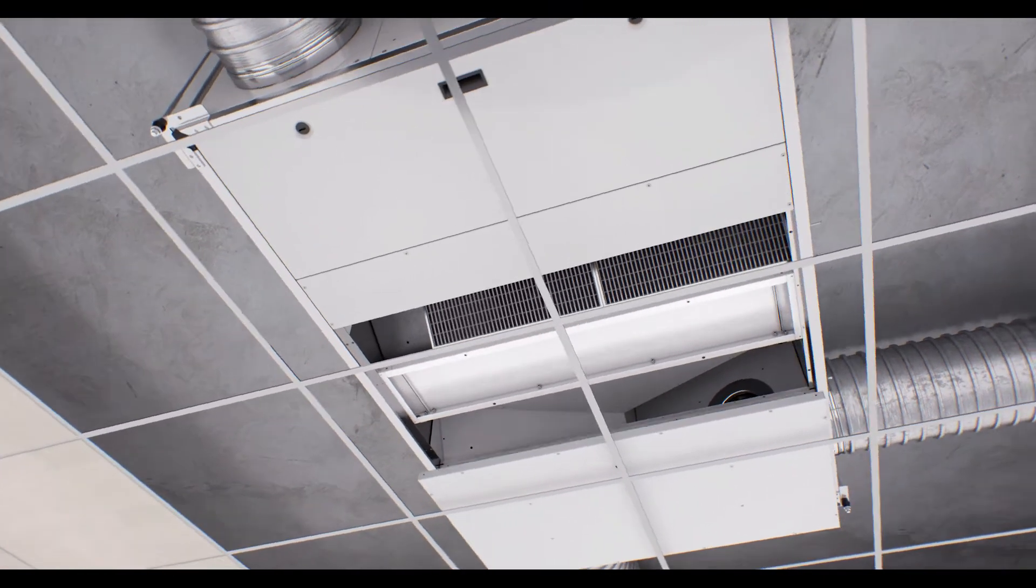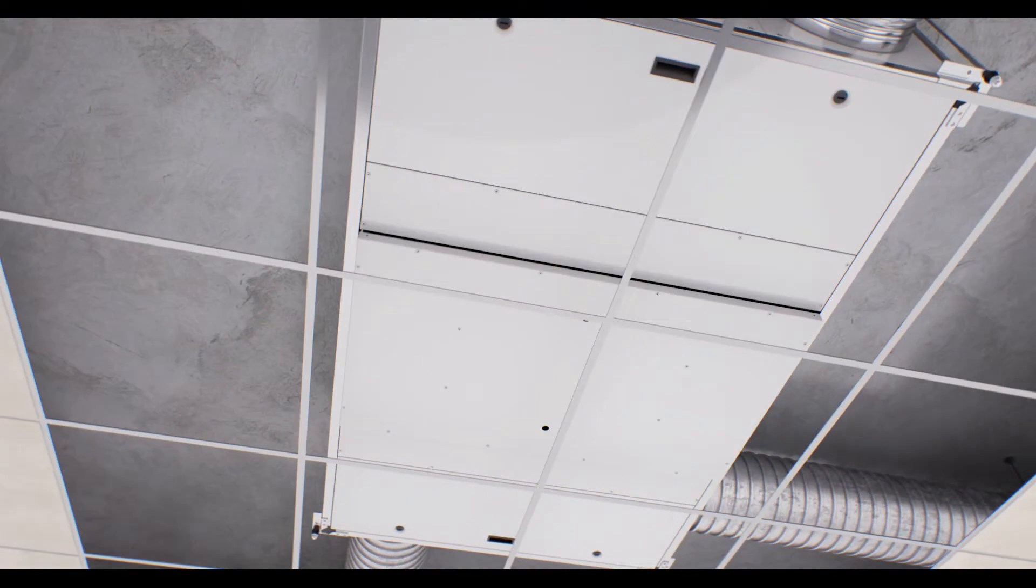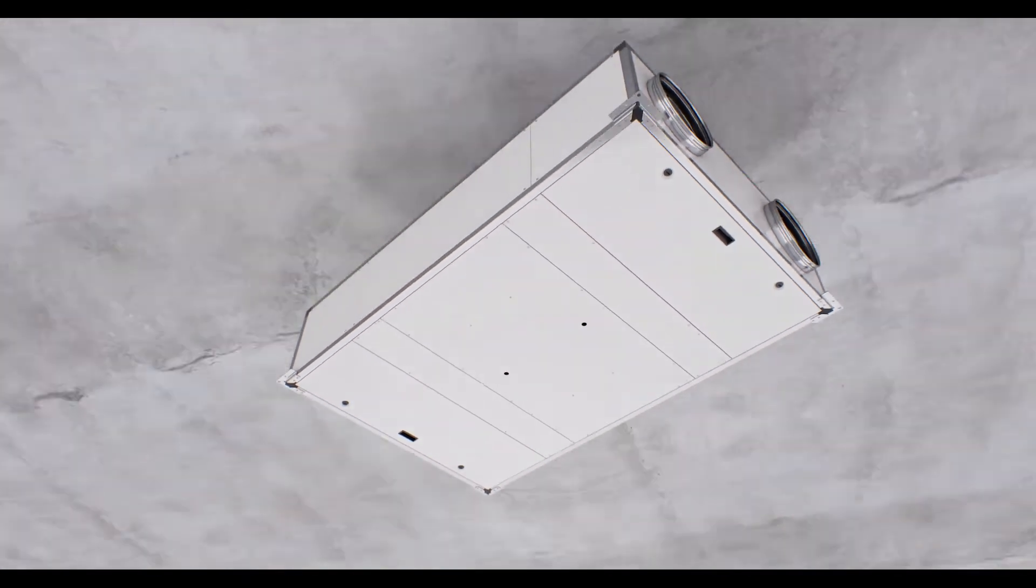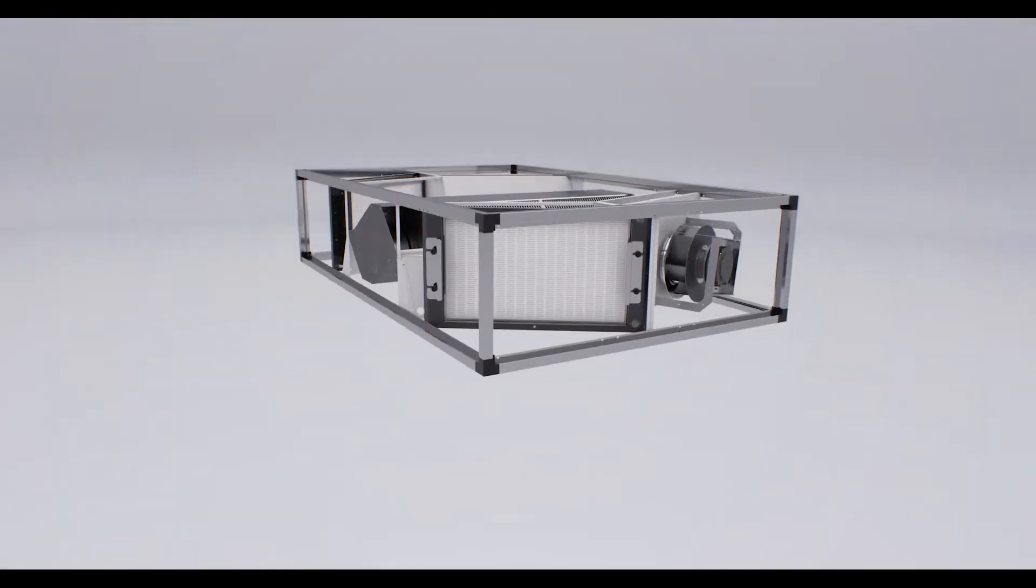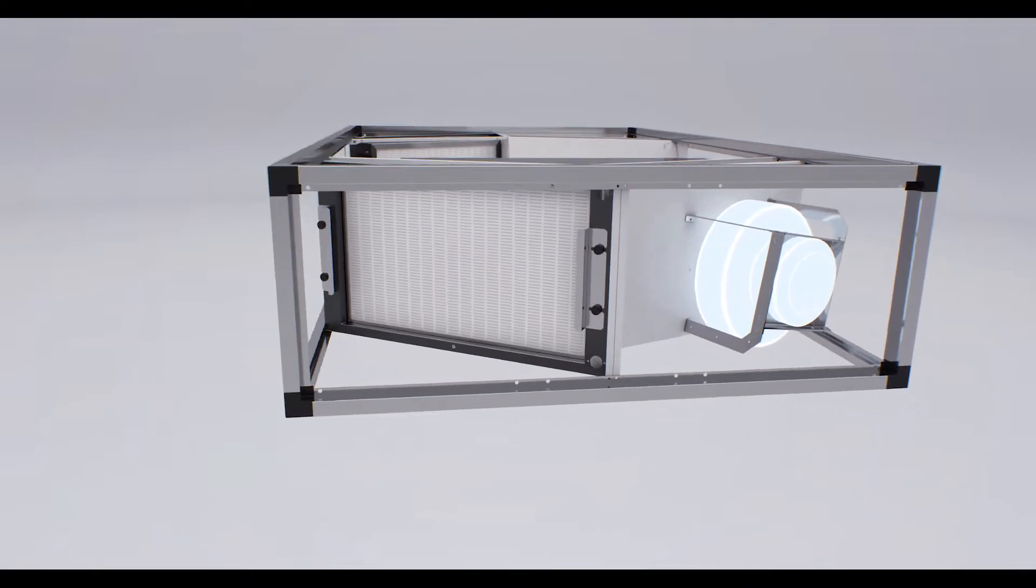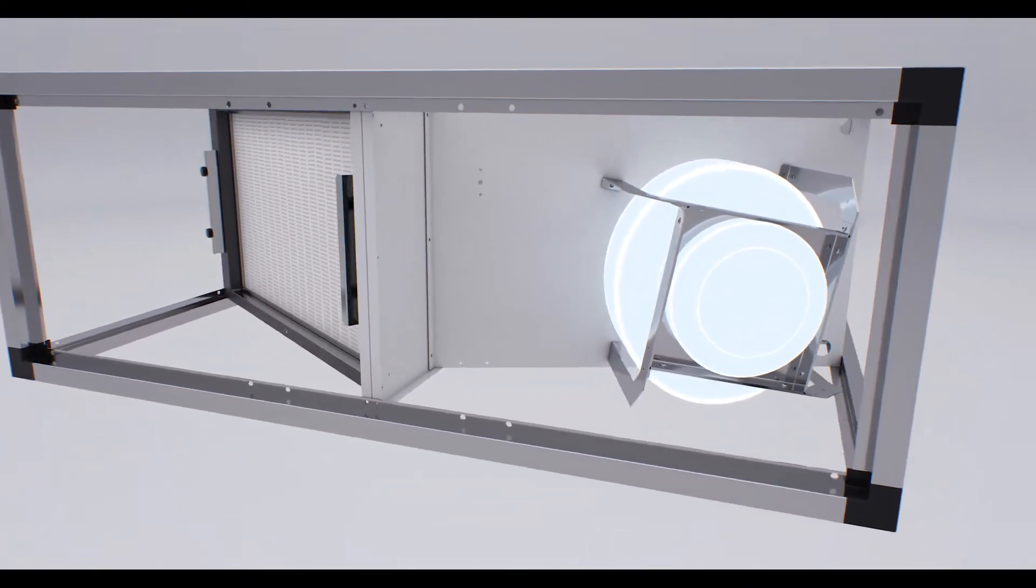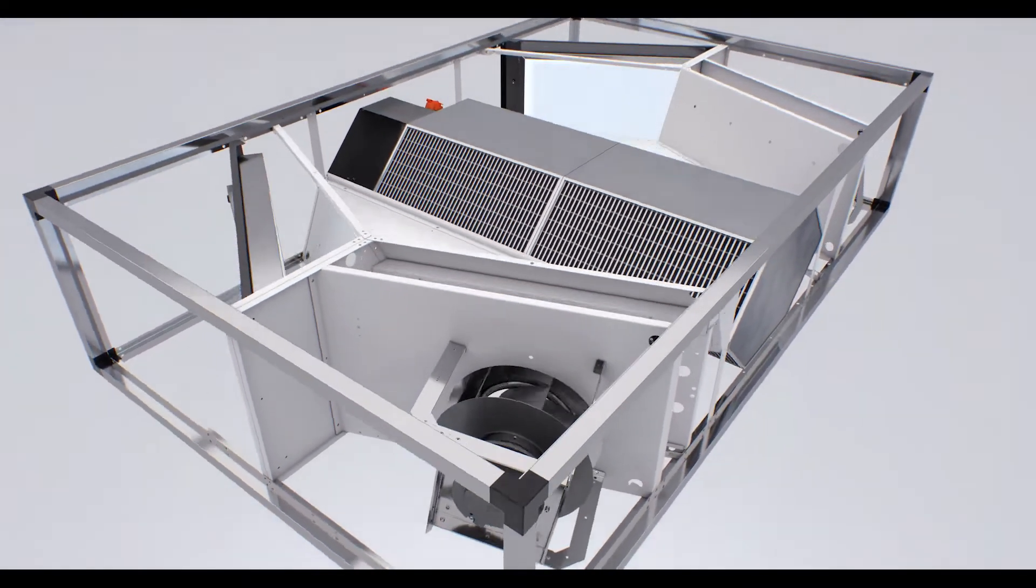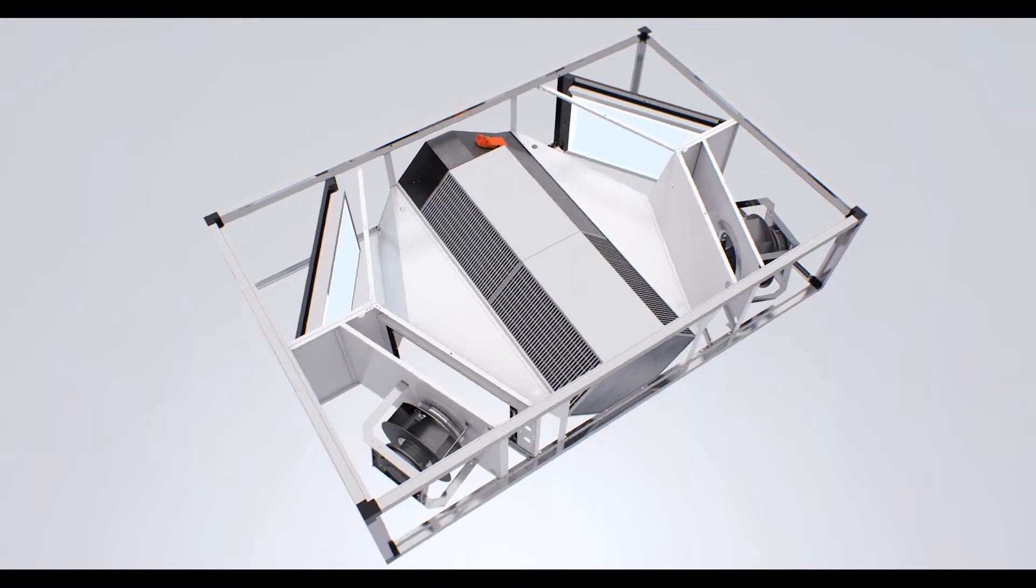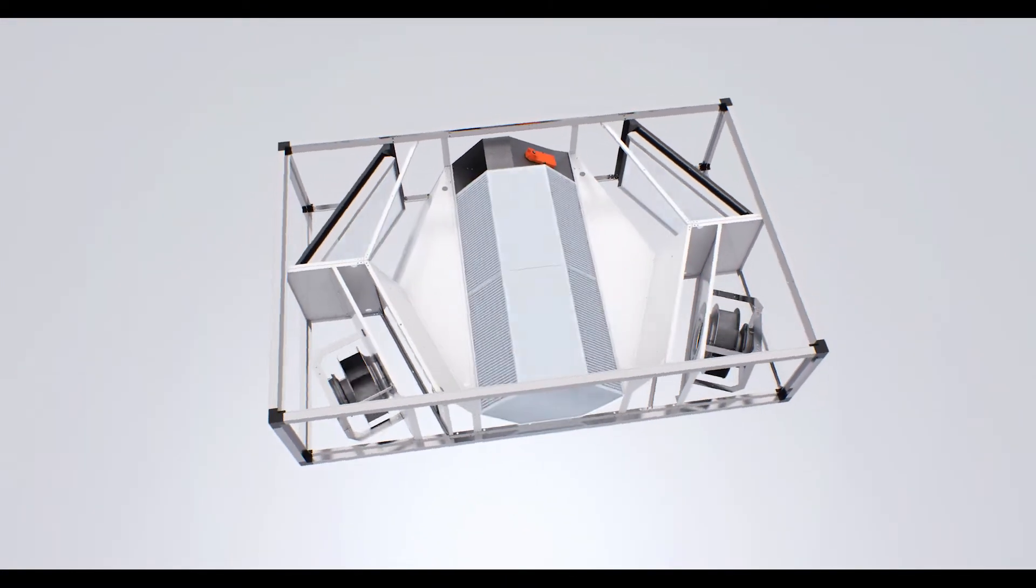The CADB HE line offers high performance thanks to the following features: high efficiency fans with low power consumption EC motor, very low pressure loss filters, F7 for supply air and M5 for extract air.